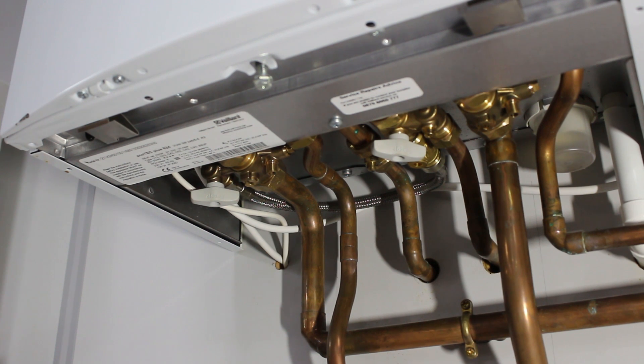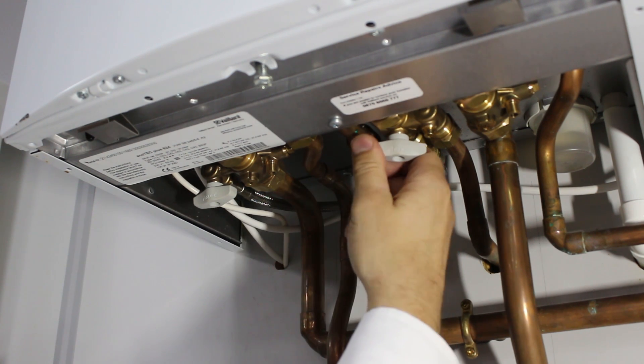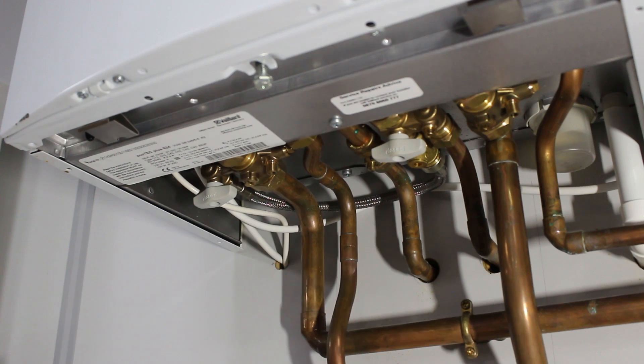When the system pressure gets to 1 to 1.2 bar, reverse the order. The left valve off, then the right valve off. Always make sure they're both in the closed position.